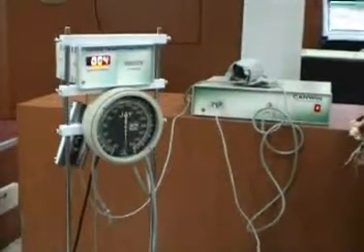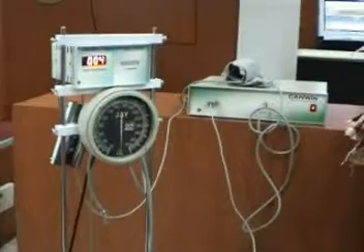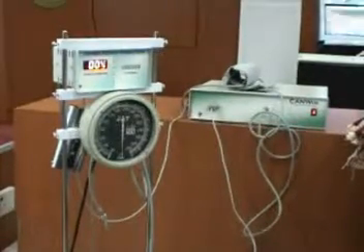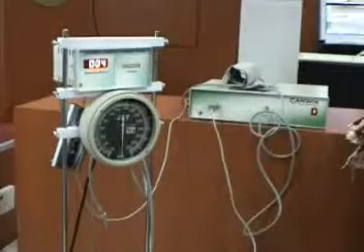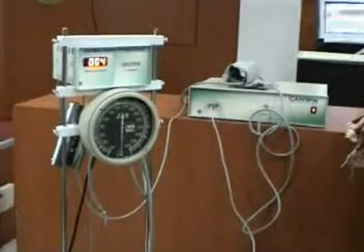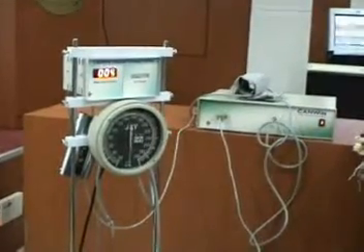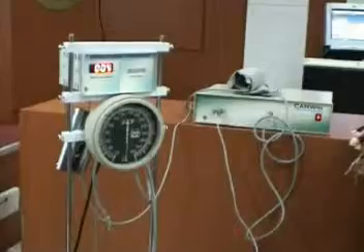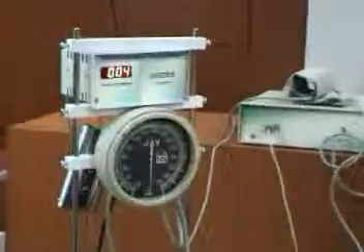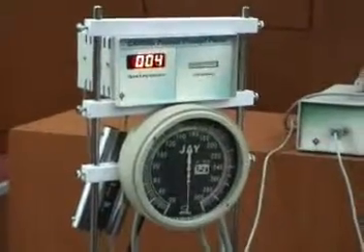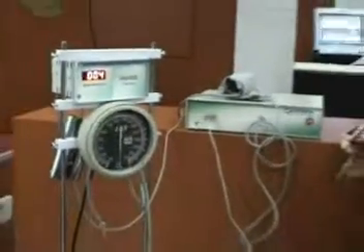Being fully automatic, CANWin eliminates the need of manual recordings, readings and calculations. Since these tests require patient cooperation, a unique patient prompt panel is provided which helps the patient intuitively. Inbuilt time domain waveform analysis and BP measurements make the task of conducting all 6 CAN tests very easy.